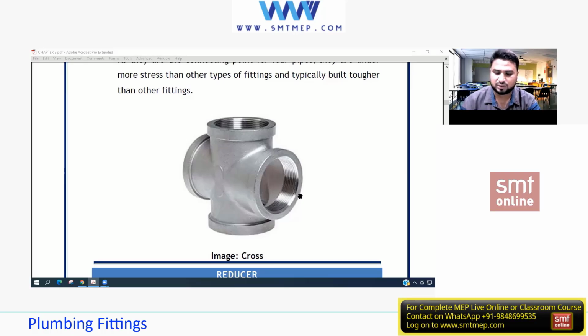This fitting is not recommended because it has the maximum pressure drop. Since it's more stressed than other fittings, it must be manufactured to very high standards with a stronger stress and strain design. Imagine one inlet and three outlets — huge turbulence is created in three different directions, causing a big pressure drop.